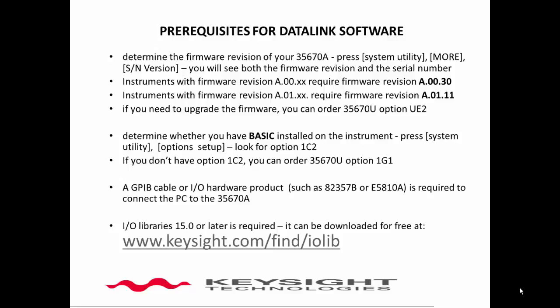If the first part of the firmware revision is A.00, you will need firmware revision A.00.30. If the first part of the firmware revision is A.01, you will need A.01.11. If you do not have the most current firmware, you can either download it from the website or you can purchase it on a floppy disk by ordering part number 35670U, option UE2.